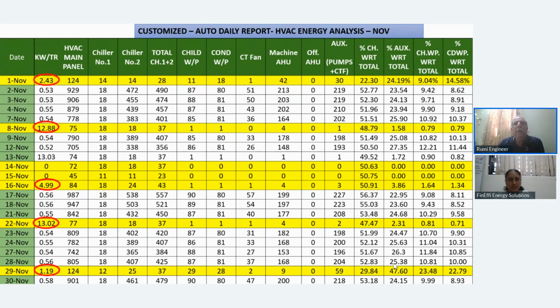What I want to bring out here is that we have to be very vigilant about all our field sensing devices — calibration of energy meters, flow meters, airflow meters, BTU meters, temperature sensors. Even BTU meters have certain sensors, and if those sensors develop a challenge, which is what happened in our case, you'll get a totally off reading.